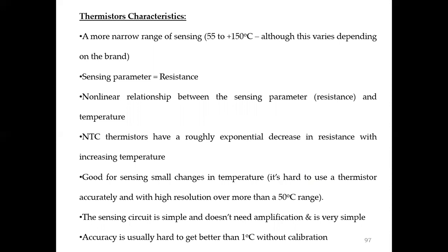NTC thermistors have a roughly exponential decrease in resistance with the increase in temperature, so they are good for sensing small changes in temperature. It is hard to use a thermistor accurately and with high resolution over more than a 50-degree range. The sensing circuit is simple and doesn't need amplification.